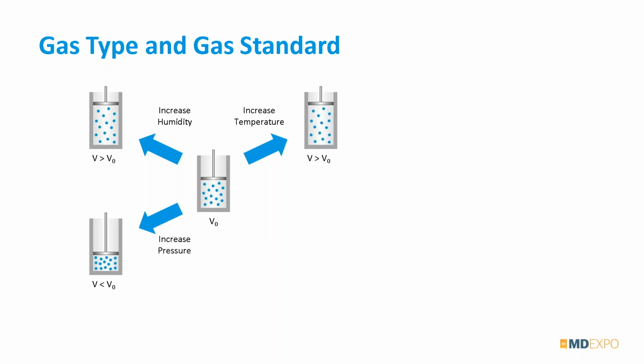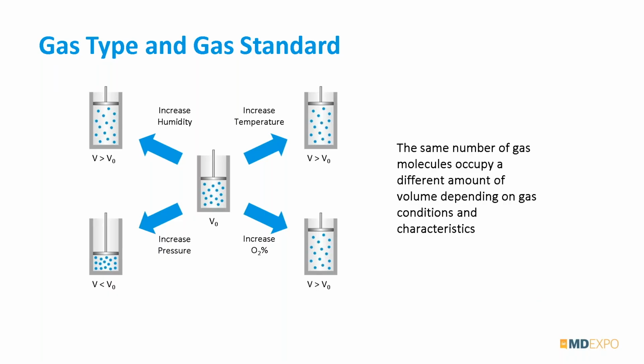So here we're changing the condition of the gas, right? So we need to know what that is so that we can measure it with our analyzer. Okay. We also can change the characteristic of the gas by changing the gas mixture. We may have just air, we may have just oxygen, or we have some mix in between. In some cases, you might also measure other gases, but in most cases, we're talking about either air or oxygen or some mix of those two. But either way, if you change the concentration of oxygen, you're going to actually increase the volume a little bit, okay? So we have the same number of molecules in our container, but depending upon the condition and the characteristics of that gas, the volume might change, okay? Why is it important for us to measure accurate volumes? What's that? Exactly, patient safety, right? We want to make sure that we give the patient enough gas, but not too much gas because we can injure them, okay?